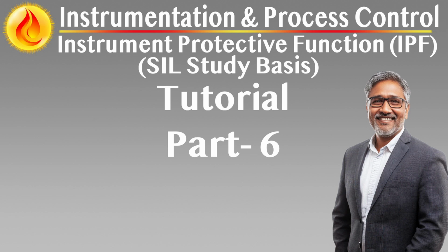Types of maintenance overrides. Signal simulation or forcing, used to simulate sensor values or final element feedback during functional testing, must be tightly controlled to prevent false logic activation or masking of true conditions. Bypass of logic conditions temporarily disables specific trip paths or interlocks. It requires logic solver access, engineering approval, and defined fallback procedures.